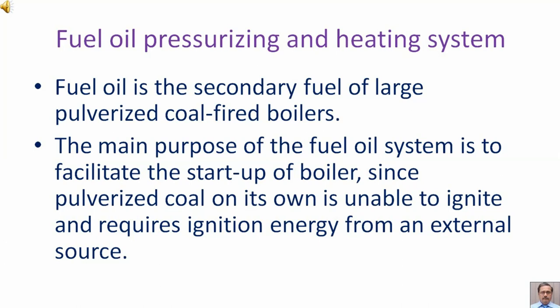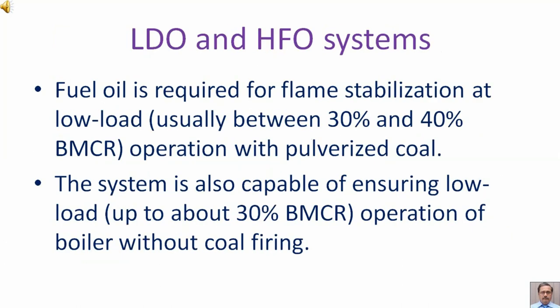Fuel oil is required for flame stabilization at low load. Low load is usually between 30% and 40% of the BMCR. The system is also capable of ensuring low load operation of the boiler without coal firing. Low load of the boiler is up to 30% of boiler maximum continuous rating.